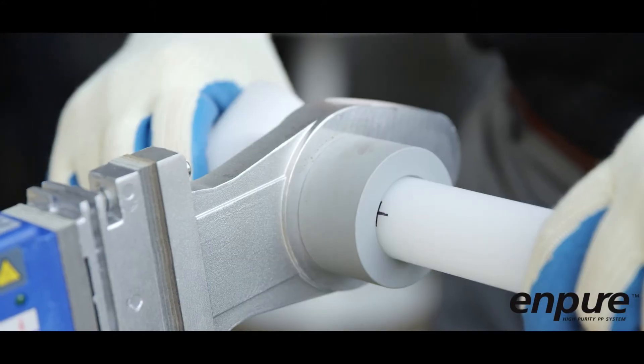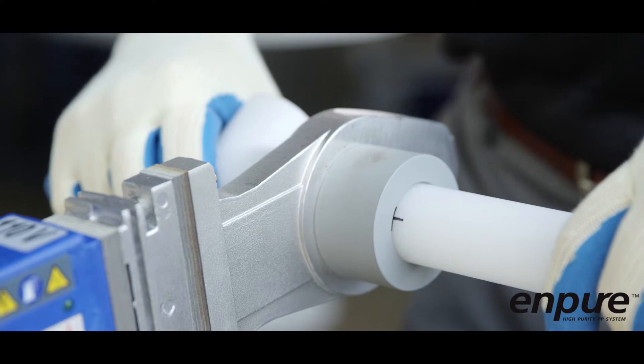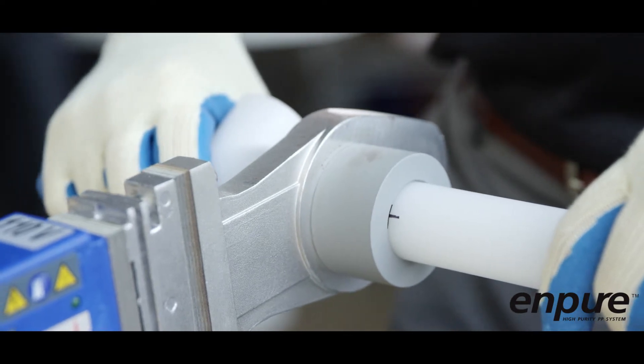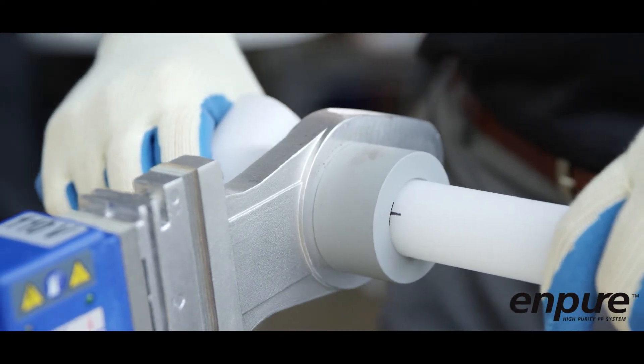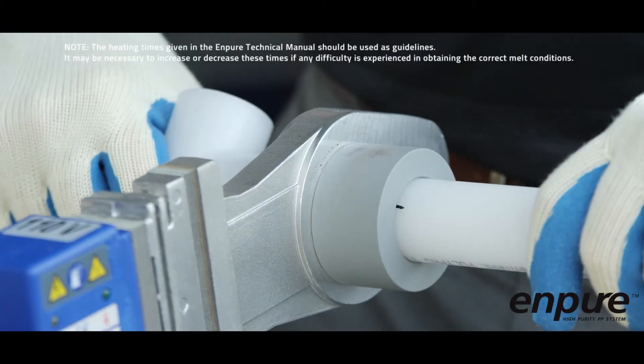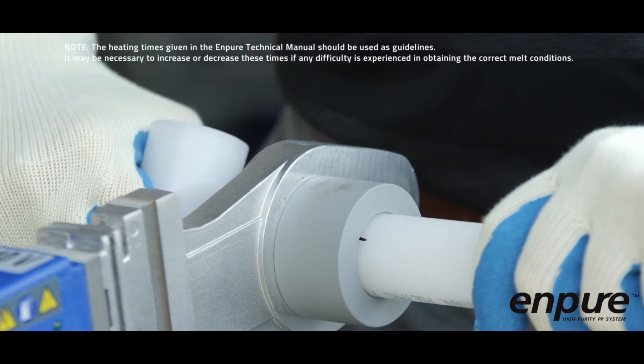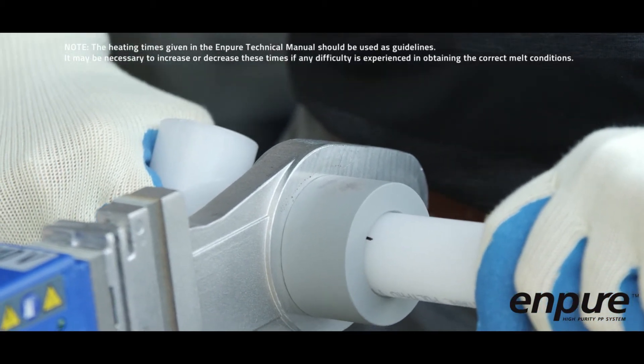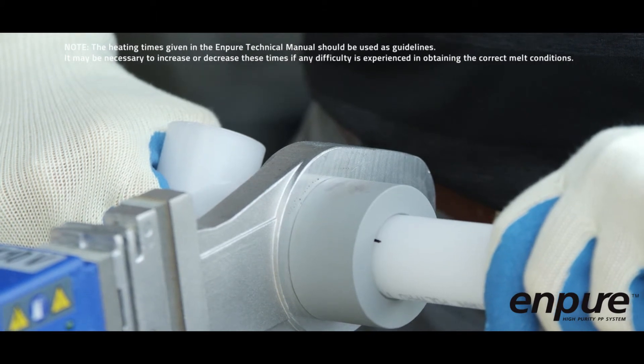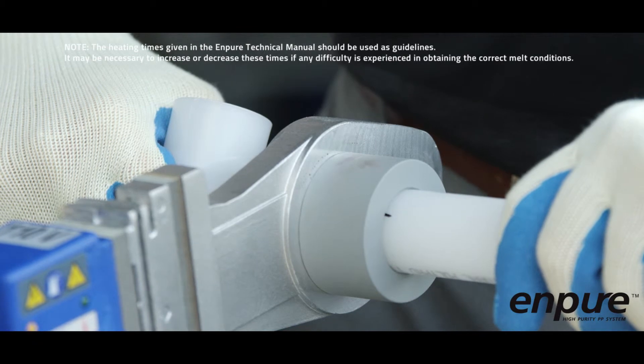Once the mark on the pipe reaches the end of the female bushing and the top of the fitting reaches the stop on the male bushing, apply just enough pressure to prevent kickback and hold together for the recommended heating times shown in the table in the Enpure technical manual. The heating time starts from the moment of full insertion of both the pipe and fitting. If the pipe and fitting do not fit tightly on the heater bushings, the heating time should start when the components have swelled just enough to contact the surface of the heater bushings.